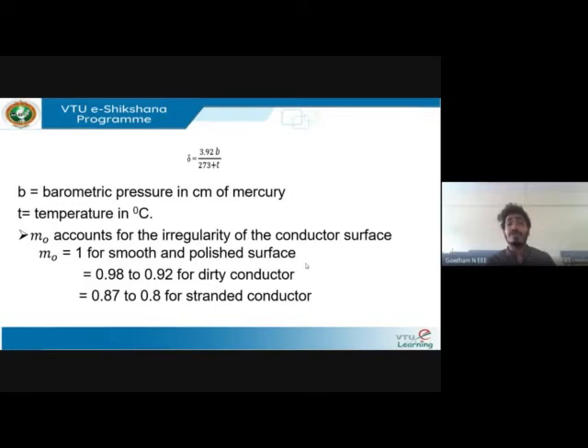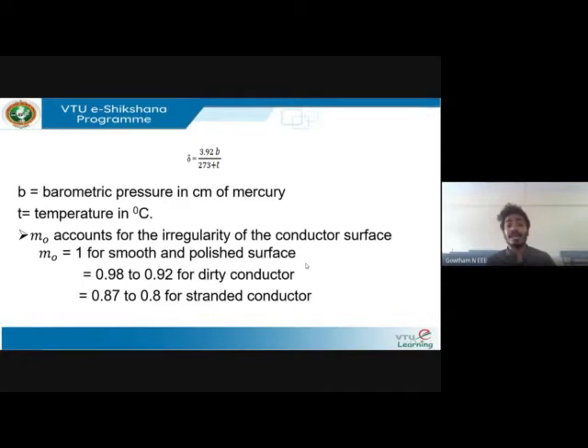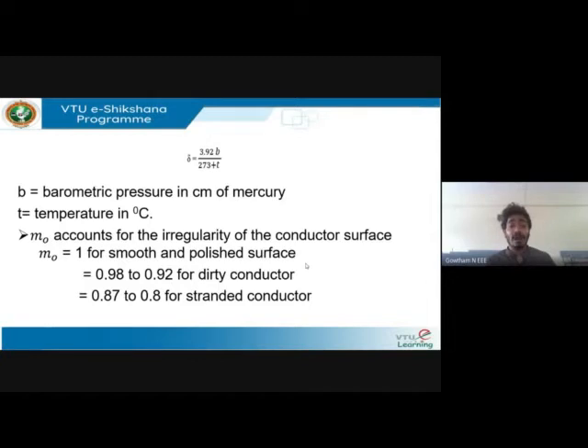m₀ is the irregularity factor of the conductor surface. If smooth and polished, m₀ = 1. If dirty with dust, m₀ = 0.98 to 0.92. For stranded conductors, m₀ = 0.87 to 0.8. All these factors are directly proportional to Vc — the critical disruptive voltage — and will have a significant effect on whether a corona discharge occurs.